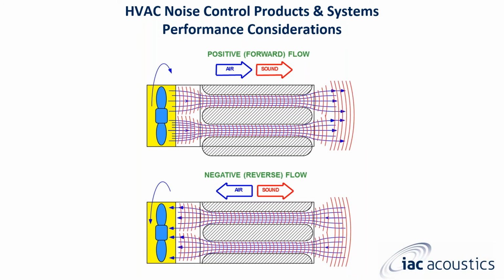Here is a really good example of flow directions. At the top, we have positive flow, also known as exhaust or supply. At the bottom, you see negative flow, commonly also known as inlet and or return airflow. Now, the difference between the two is this: with the supply airflow forward, this is a condition that exists when airborne sound and airflow are moving in the same direction.